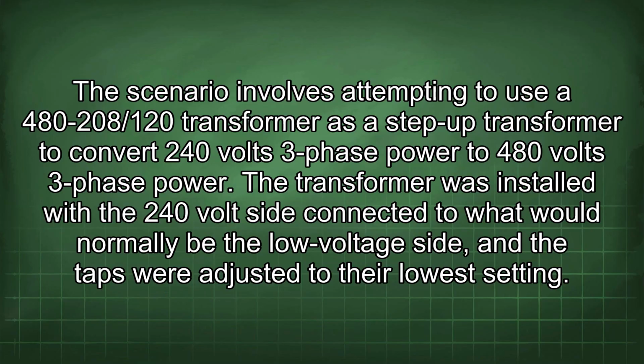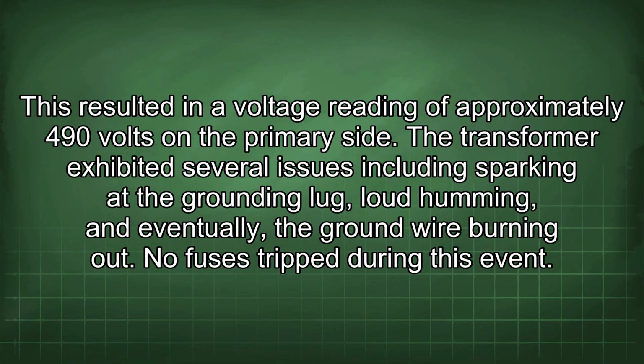This scenario involves attempting to use a 480-208/120 transformer as a step-up transformer to convert 240 volts 3-phase power to 480 volts 3-phase power. The transformer was installed with the 240-volt side connected to what would normally be the low-voltage side, and the taps were adjusted to their lowest setting. This resulted in a voltage reading of approximately 490 volts on the primary side.